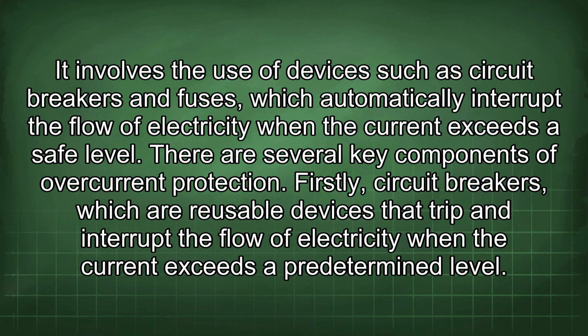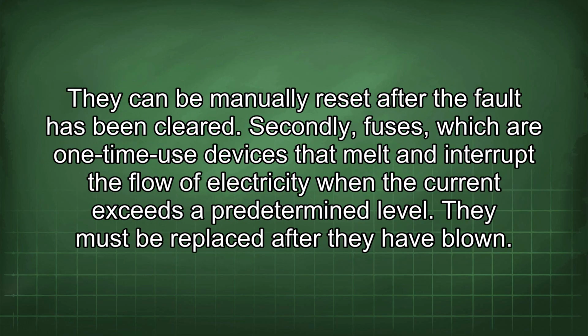There are several key components of overcurrent protection. Firstly, circuit breakers, which are reusable devices that trip and interrupt the flow of electricity when the current exceeds a predetermined level. They can be manually reset after the fault has been cleared. Secondly, fuses, which are one-time use devices that melt and interrupt the flow of electricity when the current exceeds a predetermined level. They must be replaced after they have blown.